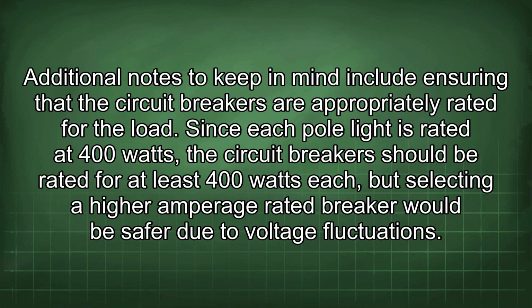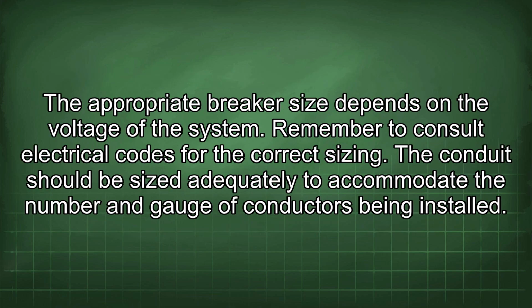Additional notes to keep in mind include ensuring that the circuit breakers are appropriately rated for the load. Since each pole light is rated at 400 watts, the circuit breakers should be rated for at least 400 watts each, but selecting a higher amperage rated breaker would be safer due to voltage fluctuations. The appropriate breaker size depends on the voltage of the system. Remember to consult electrical codes for the correct sizing.